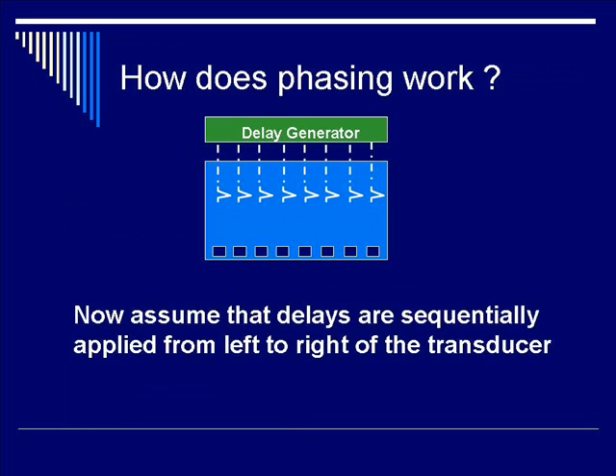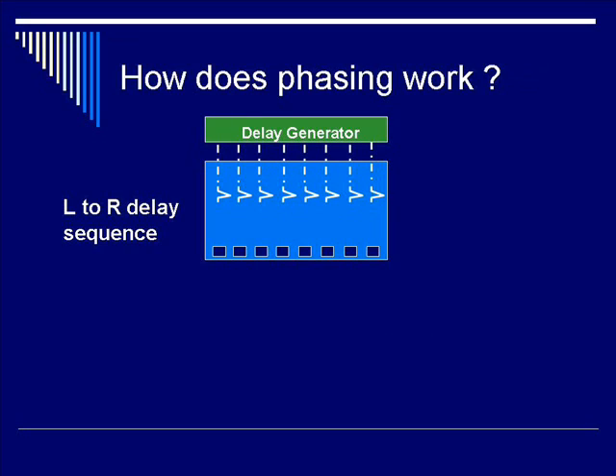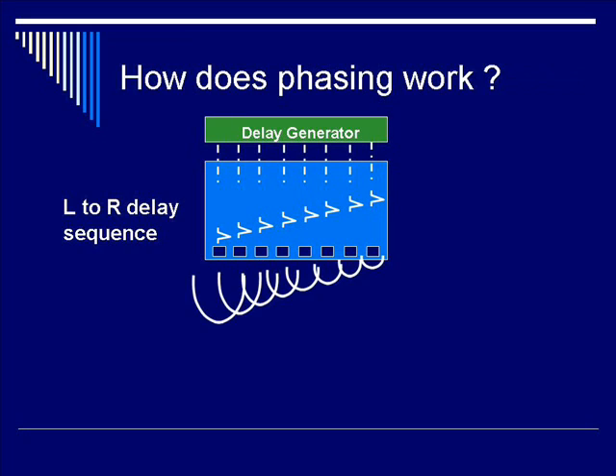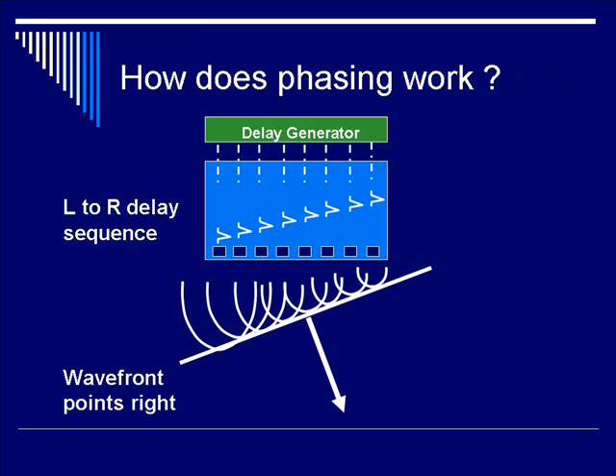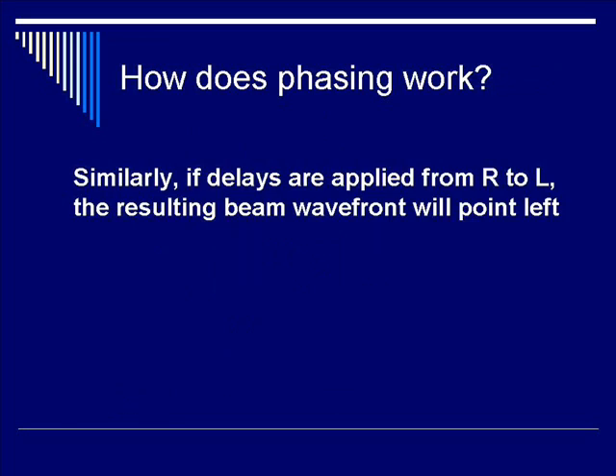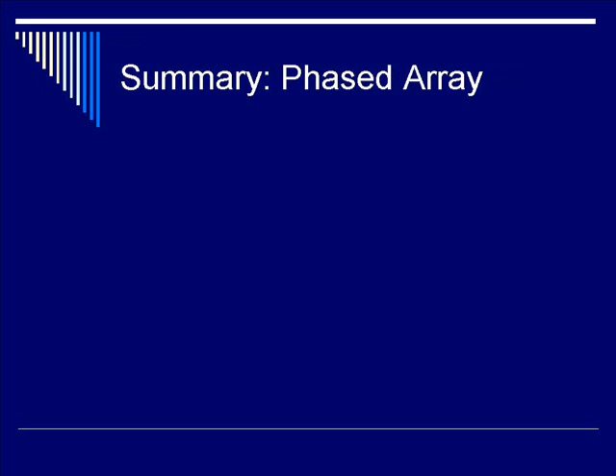So with no delays, the beam goes straight ahead. Now assume that delays are sequentially applied from left to right of the transducer — less delay on the left, more delay on the right. In this case, the ultrasound beam is far ahead on the left side compared to the right side. Therefore, the wavefront is pointing to the right as shown by the vector. As you can guess, if you flip the sequencing electronically, applying delays from right to left, the resulting wavefront will point to the left.